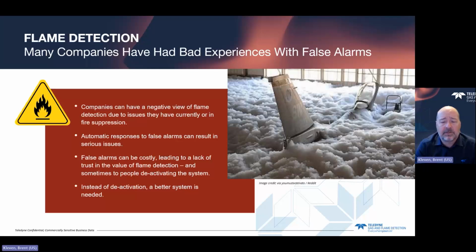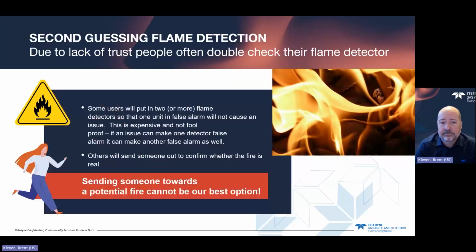So a lot of companies have had bad experience with false alarms. If you've had a situation where maybe you've dumped a suppressant, you've had something shut down that really shouldn't have been, now you've got a cleanup situation, that's not good. A lot of these automatic responses to false alarms can result in serious issues. So with the cost of a false alarm, we need to do this properly, because unfortunately a lot of people will simply deactivate their flame detection system, and that's not the right answer. We simply need a better system to make sure that we don't get these false alarms.